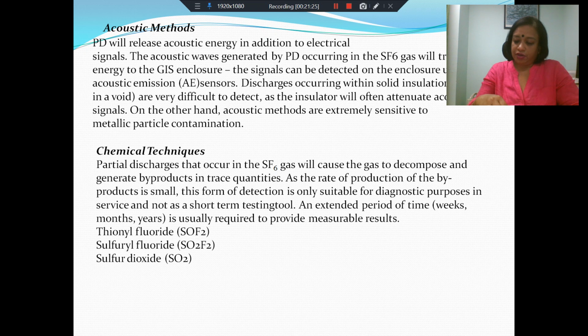In case of acoustic emission, the best kind of PD inducing defects that acoustic methods can best detect are the metallic particle contamination. So when you have signals due to metallic particles jumping, lifting off, and then bouncing on the enclosure, and then PD happening, those kinds of discharges are best measured, best detected through acoustic methods. Apart from that, we also have chemical techniques.